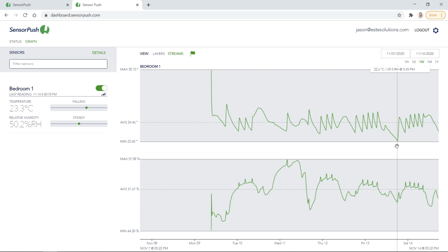And this just goes to show you how ineffective it is to have the thermostat in the living room to control the temperature in a bedroom upstairs. Before seeing this, I would assume that the temperature readings would be more of what we have in the middle of the graph here, which is tightly bound highs and lows that are only maybe 1 degree apart, to show you that when the furnace turns on, the temperature goes up, and then when it turns off, it goes down. However, I am quite surprised to see these really high peaks and these really low valleys. This must be one of those cases where something that was happening in our living room inversely affects the temperature in the bedroom upstairs.